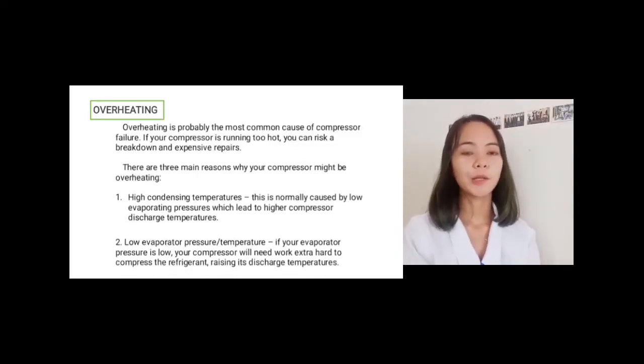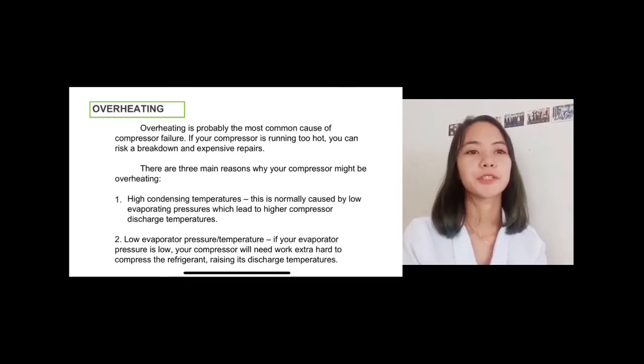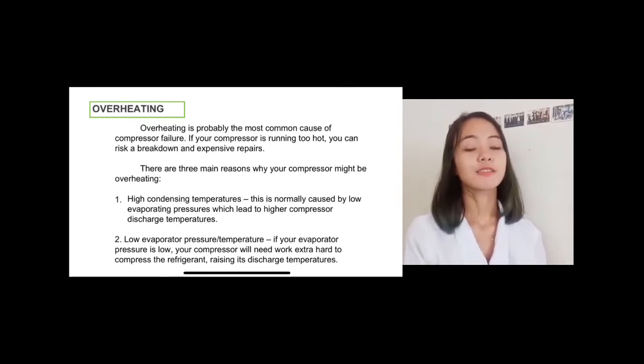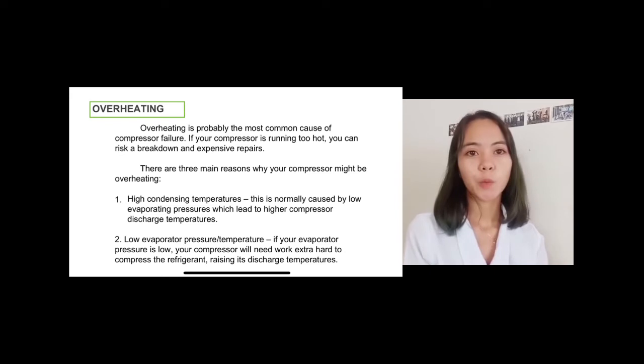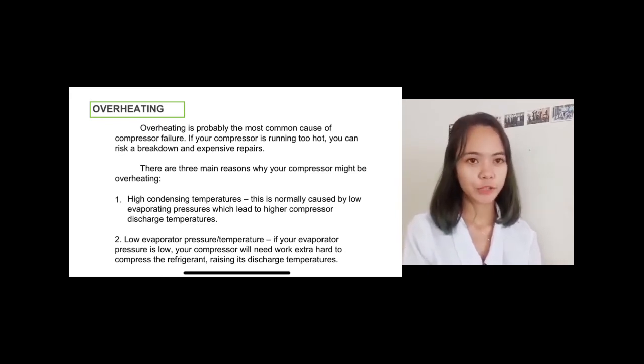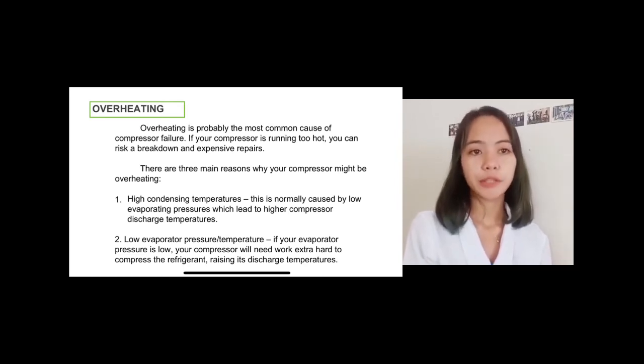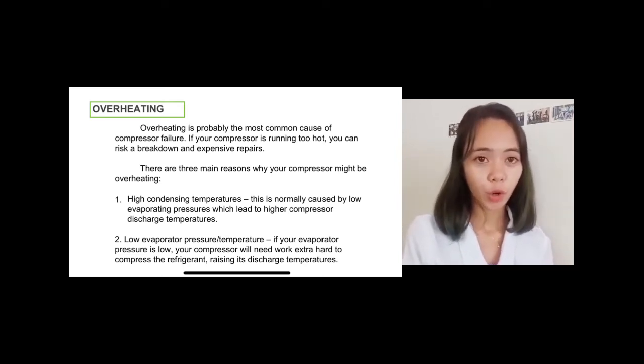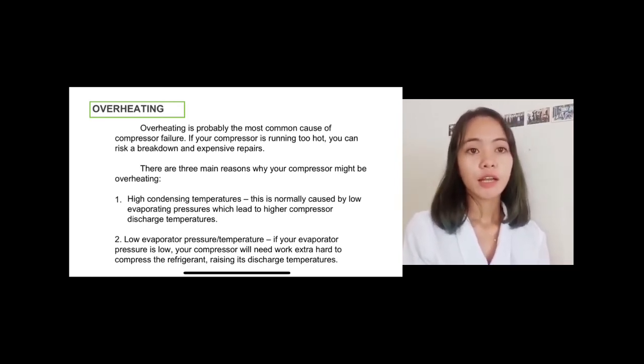The second would be the low evaporator pressure or temperature. If your evaporator pressure is low, your compressor will need to work extra hard to compress the refrigerant, raising its discharge temperatures. The reasons would be dirty or iced over evaporator coil, dirty air filter, insufficient airflow, evaporator fan motor malfunction, defrost component malfunction, undercharged refrigerant, and wrong refrigerant.